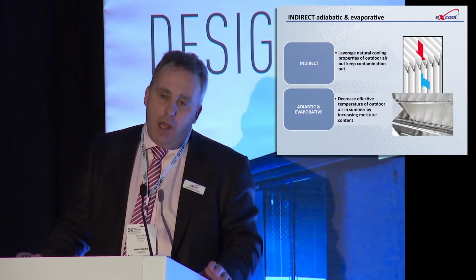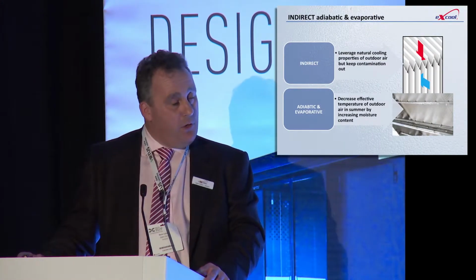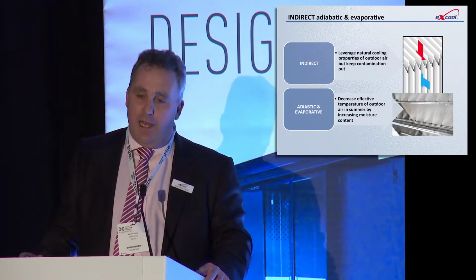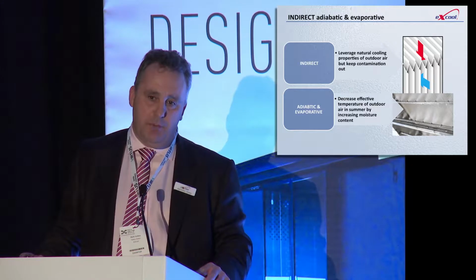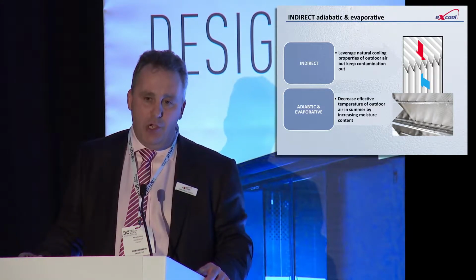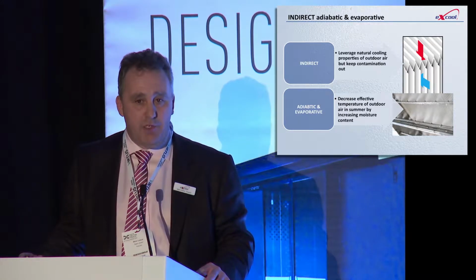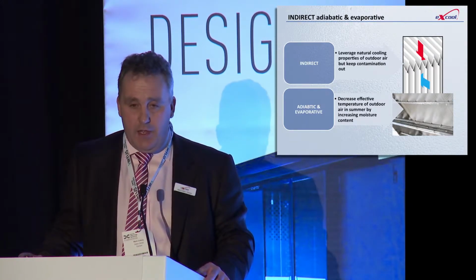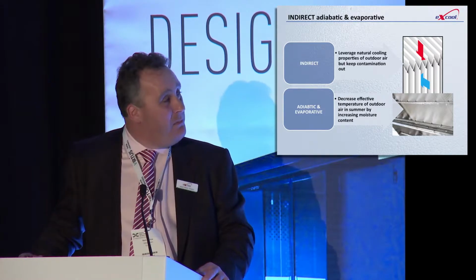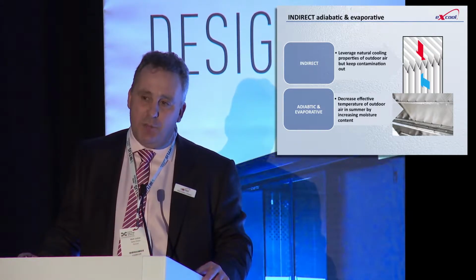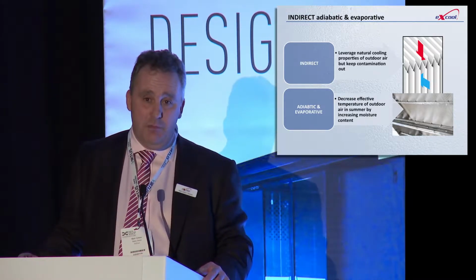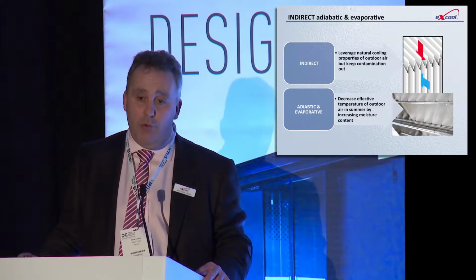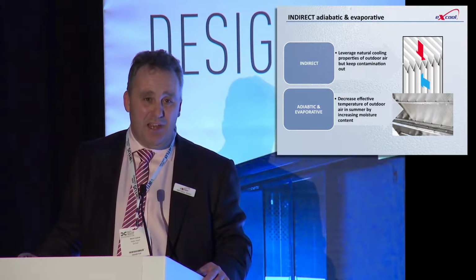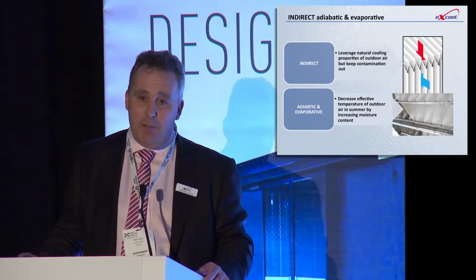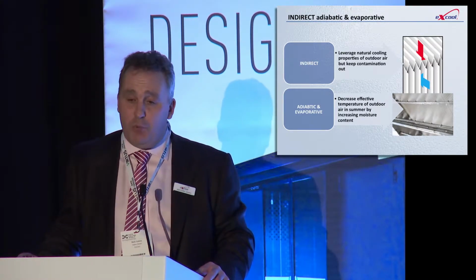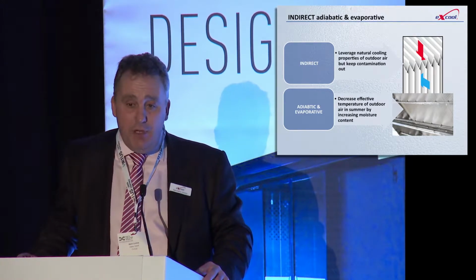We do that in a fairly unique way. It was unique 3 years ago, but there are a few competitors coming to the market now. We use an indirect system for cooling. So we're using outdoor air as a cooling medium, but we're not introducing that outdoor air into the space. It's really important that you get that in your head, because as soon as you start introducing outdoor air into the space, you bring the compressors back into the system, because you cannot rely on outdoor air all year round. No matter who you are or what you're doing, if you're bringing outdoor air into the space, there's a chance that there might be poor air quality, such as a fire, which means you need compressors. So we use outdoor air purely as a cooling medium.